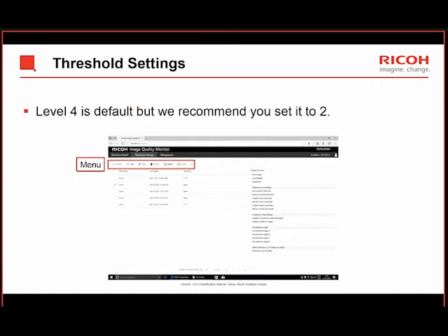What we're recommending is you set this to level 2 - not the loosest level, but the next level up, which will detect things the human eye can see. Level 4 will detect things the customer would never see. So that's why we're recommending you change the setting to level 2. Please make sure you do this. The unfortunate thing is customers can change it, so the customer can change it to level 5. If they do that, you'll be there a lot while they're using this system. So instruct the customer not to change the level setting. Leave it at level 2 and tell them to leave it alone, don't play with it.